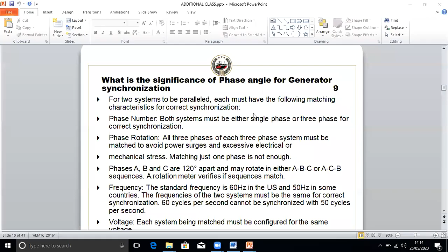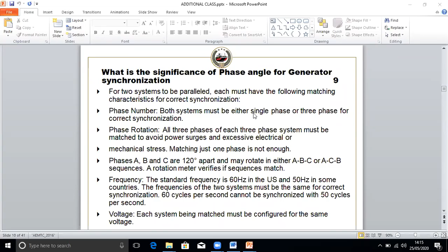What is the significance of phase angle in generator synchronization? You see, when two systems are to be paralleled, each must have the following matching characteristics. Both should be three phase, and phases A, B, C are 120 degrees apart and may rotate in ABC or ACB sequence. The standard frequency is 60 Hertz. Frequencies of the two systems must be the same for correct synchronization. And voltage, each system must be configured for the same voltage.